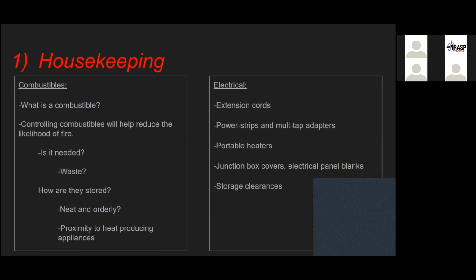And usually the best way to determine if it is overcurrent protected is it's got a fuse or a switch. So if you were to overload that outlet or that strip, it's going to shut itself off. It's not going to allow you to continue to draw excess power through that building electrical system, therefore heating up the wiring within the walls.